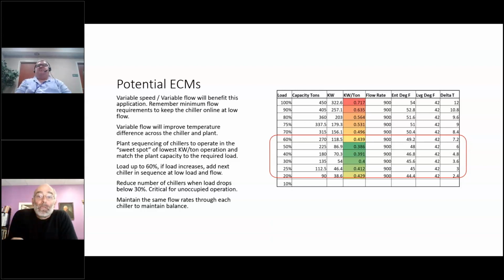And that kW per ton is just for the machine, the chiller itself. Right. You're also going to have to add the energy you use in those pumps running at 50%. If you believe the horsepower follows the cube of the flow, that goes down to a level where you're pumping a lot less water. The pumps have an easier time pumping lower flow than 100% flow.